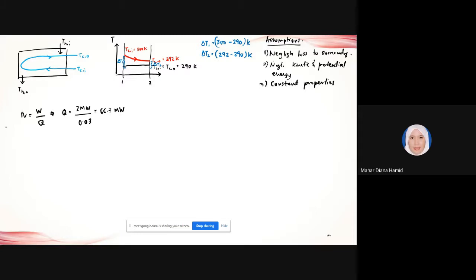Next, we need to calculate the delta T, the LMTD. So delta T LMTD equals delta T1 minus delta T2, over ln of delta T1 over delta T2. If you substitute everything into this equation, you'll get around 5 Kelvin. It doesn't matter, because this is a delta, so it's also equal to 5 degrees Celsius.